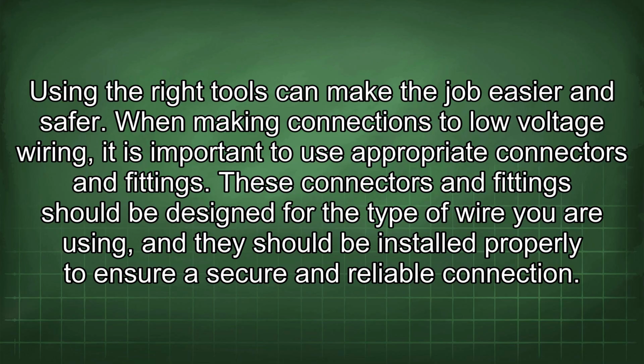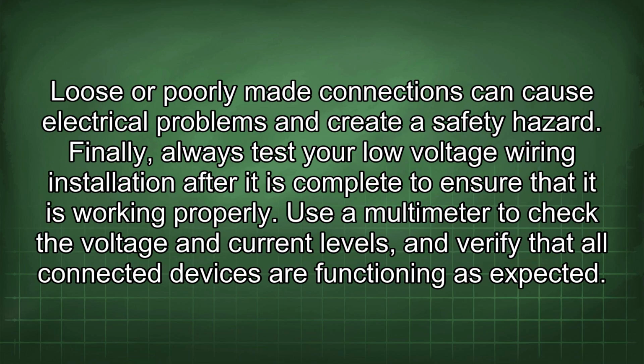When making connections to low voltage wiring, it is important to use appropriate connectors and fittings. These connectors and fittings should be designed for the type of wire you are using, and they should be installed properly to ensure a secure and reliable connection. Loose or poorly made connections can cause electrical problems and create a safety hazard.